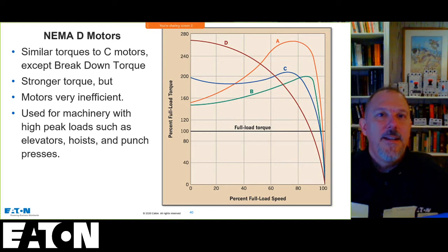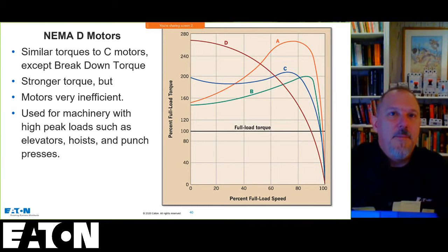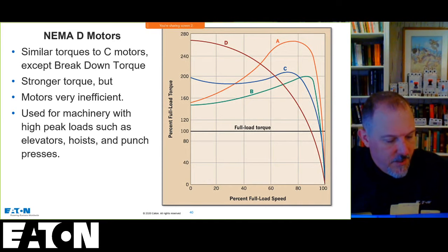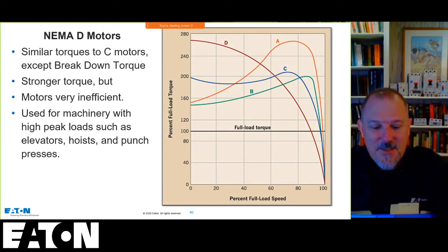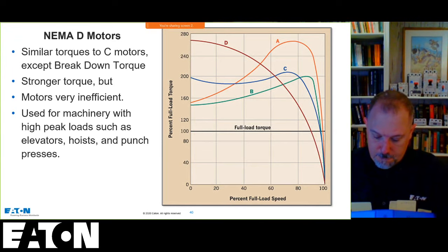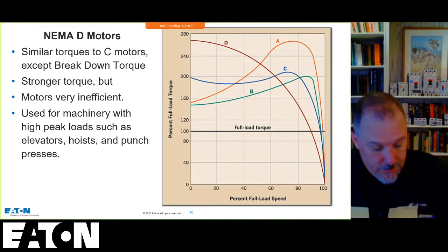He's the man. If the nameplate full load current value is higher than the table values, should the nameplate value be used? See, last sentence of 430.6(A)(1). So, Bob Fahey, good point. Let's take a look at 430.6(A)(1). This is what I love about the code and love about my tubers. So 430.6 is ampacity and motor rating determination. A is general motor applications. So this applies to all.